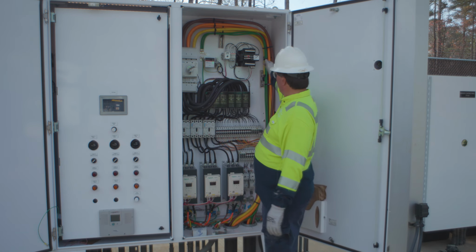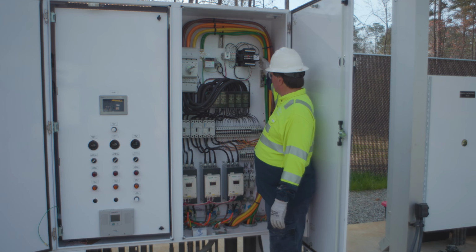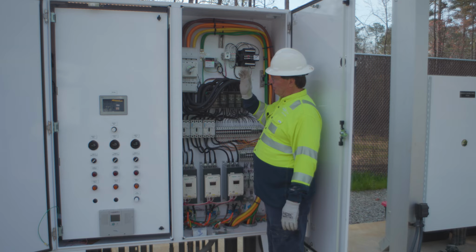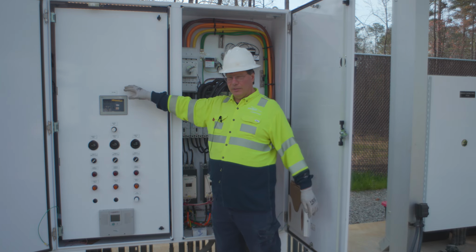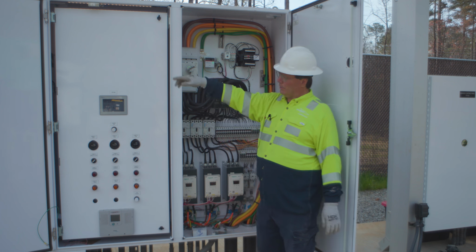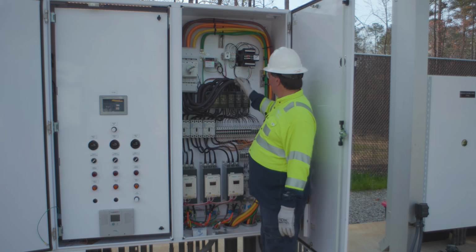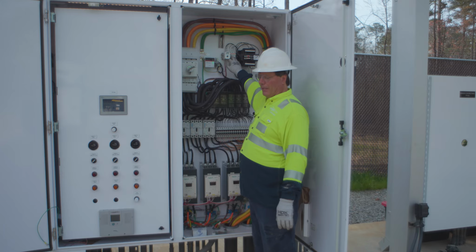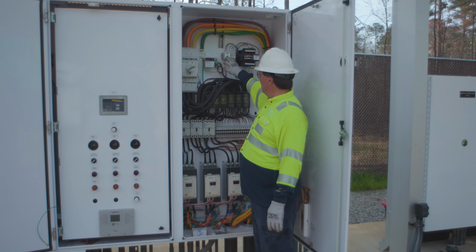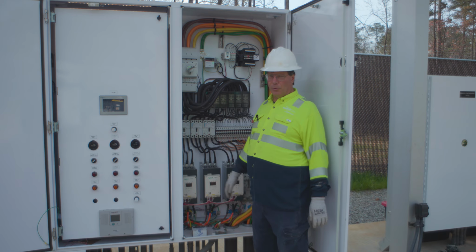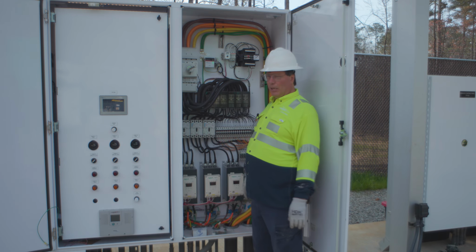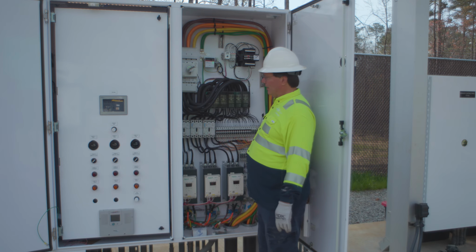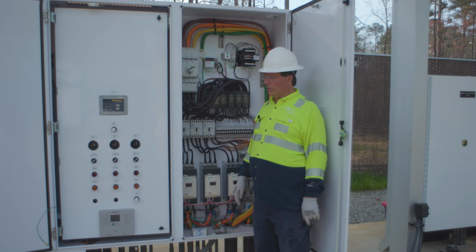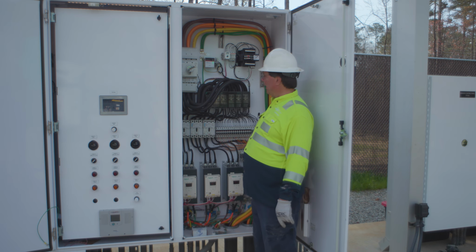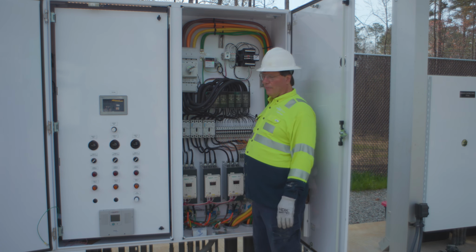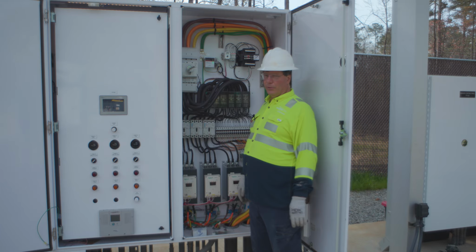Up here in the upper corner, you have a control power transformer. This control power transformer is for this control panel, as well as the PLC control panel. There's three-phase fuses here that go to our phase monitor. A green light, steady, is normal. If it's flashing, it's in the process of starting. If it turns red and is solid, that means the phases are reversed. If it turns red and flashes, you either have phase loss or a low voltage condition.